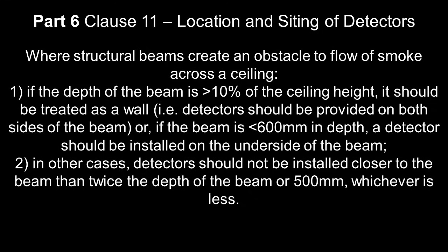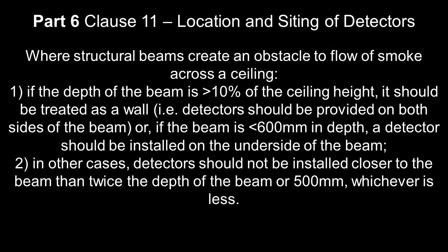Where structural beams create an obstacle for the flow of smoke across the ceiling: if the depth of the beam is more than 10% of the ceiling height, so for example, if you've got a 2.6 metre high ceiling and a 300mm beam, it should be treated as a wall. So in that case, you treat the beam as a wall, i.e. a detector should be provided on both sides of the beam.